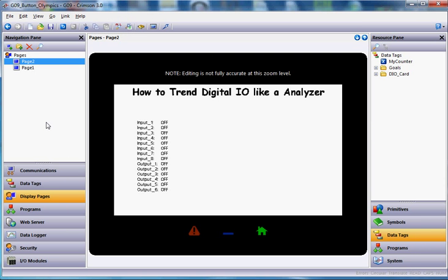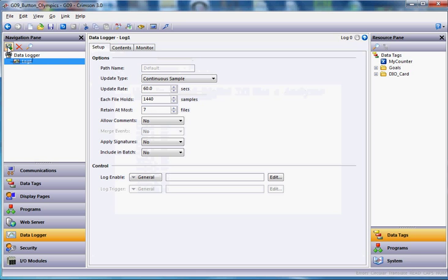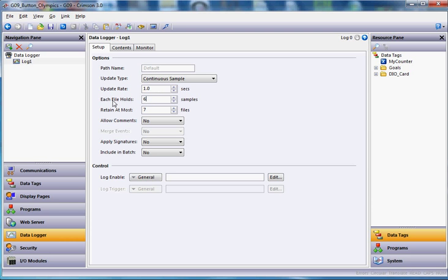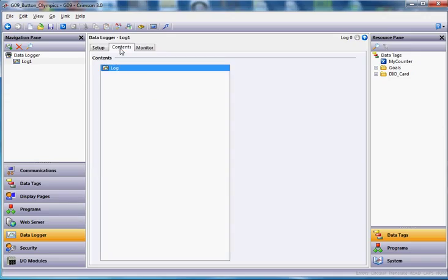If I go back here to Crimson, and let's say I want to show this on a data logger. So I'll go over here to the data logger section here. I'll create a very simple log file. The fastest we can log is once a second, so I'll change that to once a second. I'll make each file for this example hold 60 samples, and maybe I want this thing to have the last 10 minutes of data. So once a second is the update rate here. Each file holds 60 samples, and I've got to retain at most 10. So after 10 minutes goes by, we will delete the oldest file with the next newest. If I go to the Contents tab here, this is where you tell it what you want to log.